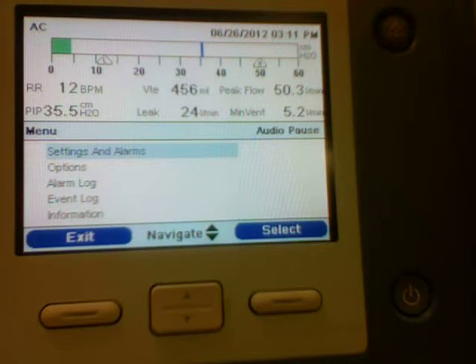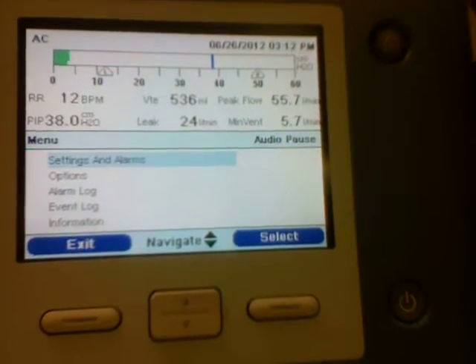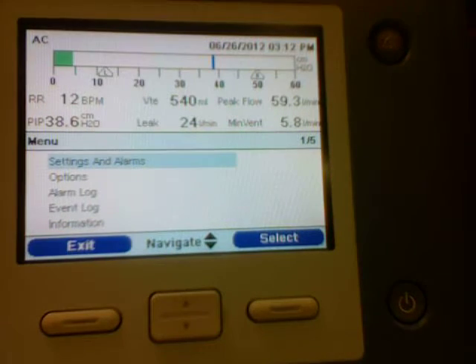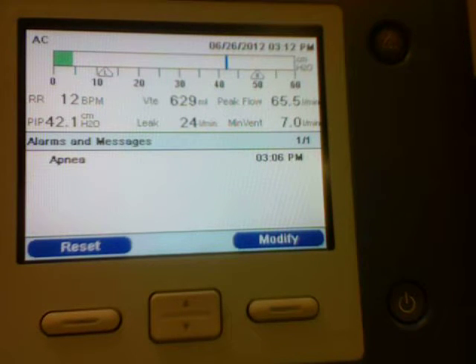If I think it's too fast, I can go down and lengthen my inspiratory time. But if I feel like I'm not achieving my volume, and you can see that right here, I have it set on 700. It looks like I'm getting back about 540. We'll give the ventilator a minute and see if it can catch up. Yeah, it looks like it's trying to auto track, auto adjust itself to deliver the 700 relative to the amount of leak that it has. If I feel like it's not accurate enough, it's not able to achieve that, then I can always change over to the active circuit with the exhalation valve.